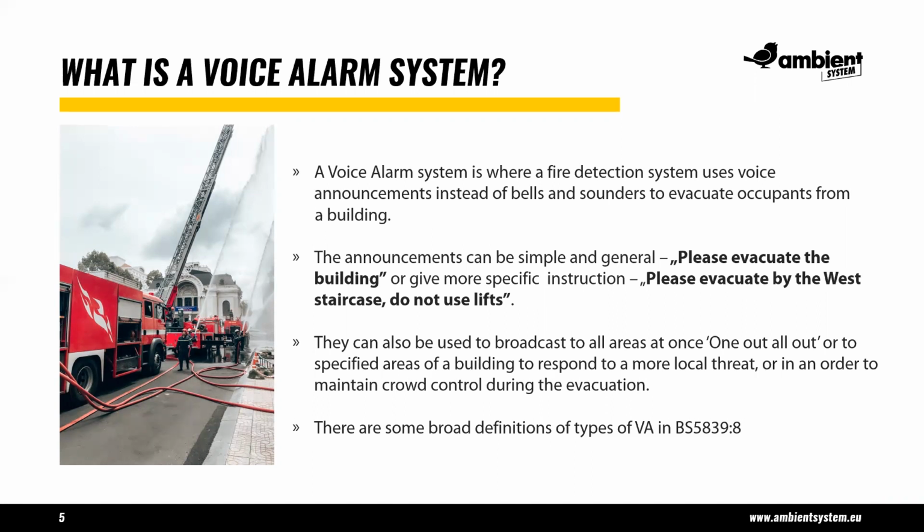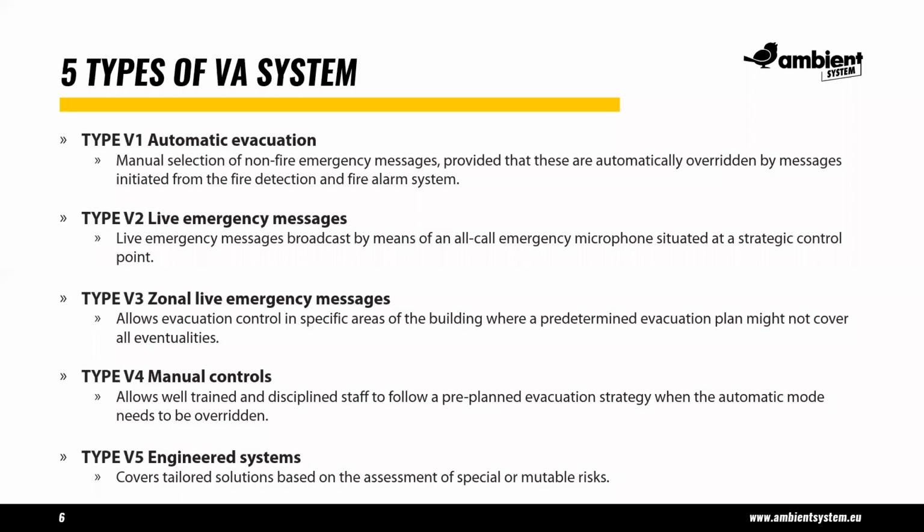And these instructions can be very simple, or in fact can be quite complicated, or quite varied depending on the number of scenarios you might have. In a large airport, for example, you might not want to evacuate people from a building, but you might want to move them away from a source of danger, and so on. So it can be quite a complex selection of responses to different fire events. And in the guiding documents for voice alarm code of practice in the UK, we have a variety of types of system which are mentioned and specified in order of increasing complexity, listed from V1 to V5.